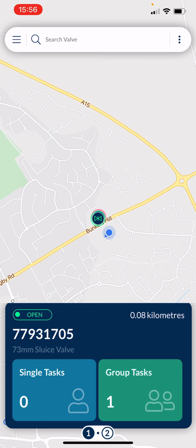It's trying to ensure that they turn the valves in a way that decreases or eliminates the likelihood of transient pressure water hammer being introduced into the network. And that's really important for a number of reasons, as we've probably already mentioned. So leaks, bursts, water discoloration, they are the key drivers. So transient pressure, water hammer is a known cause of all of these three things.